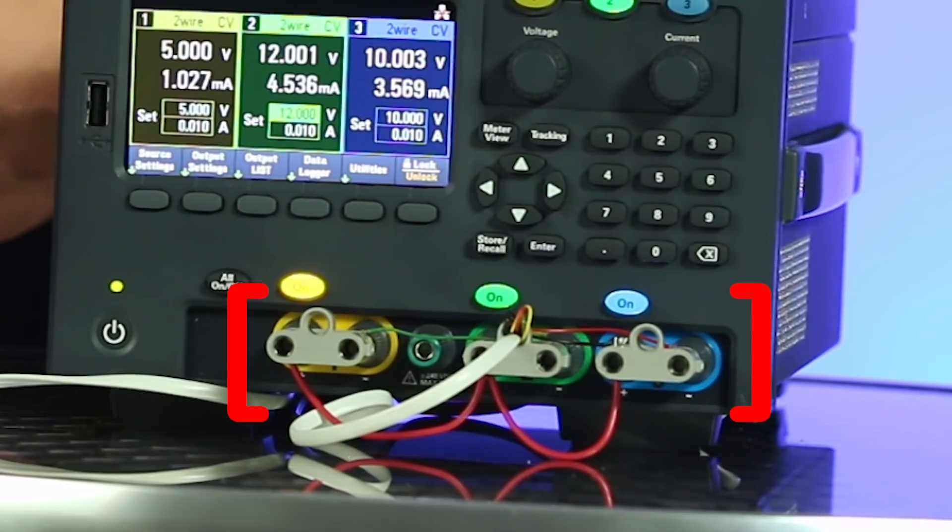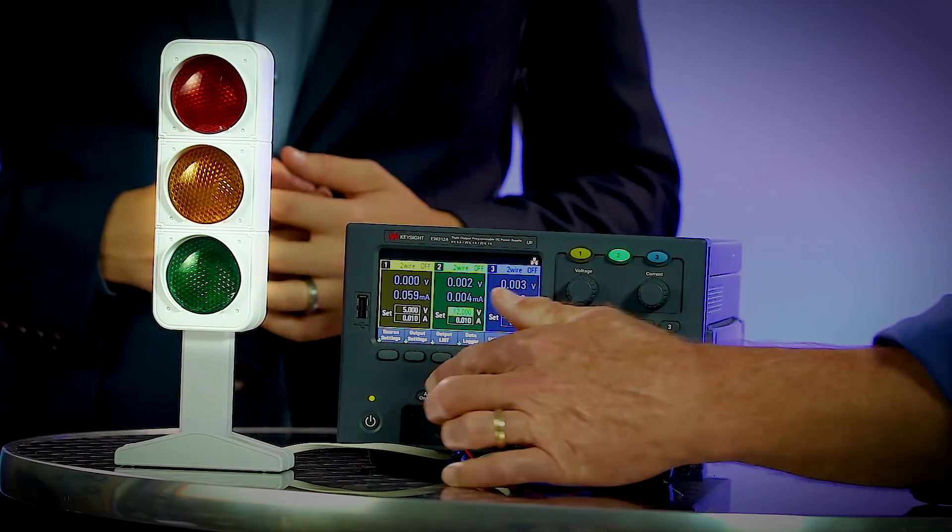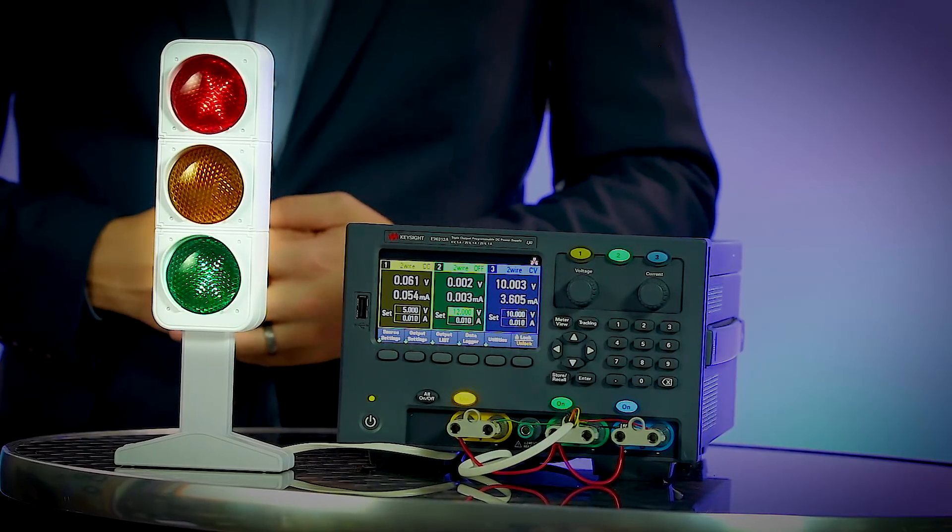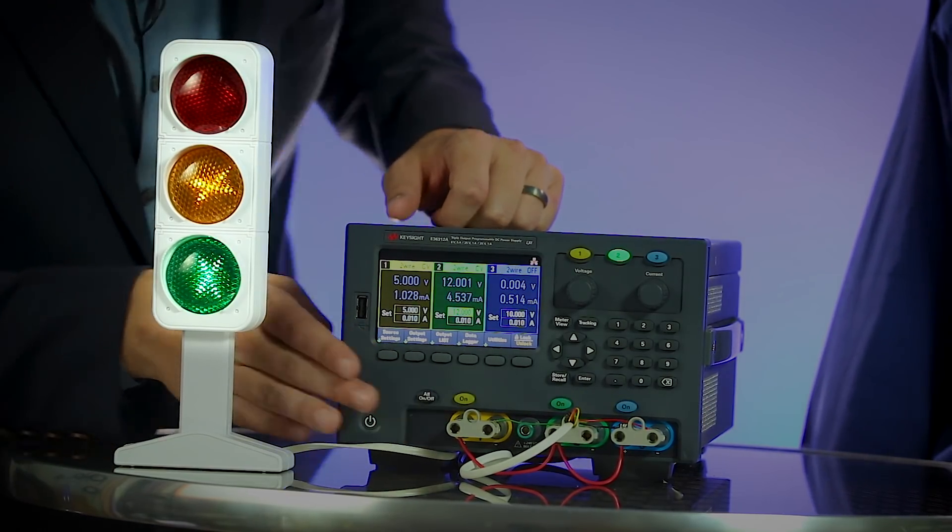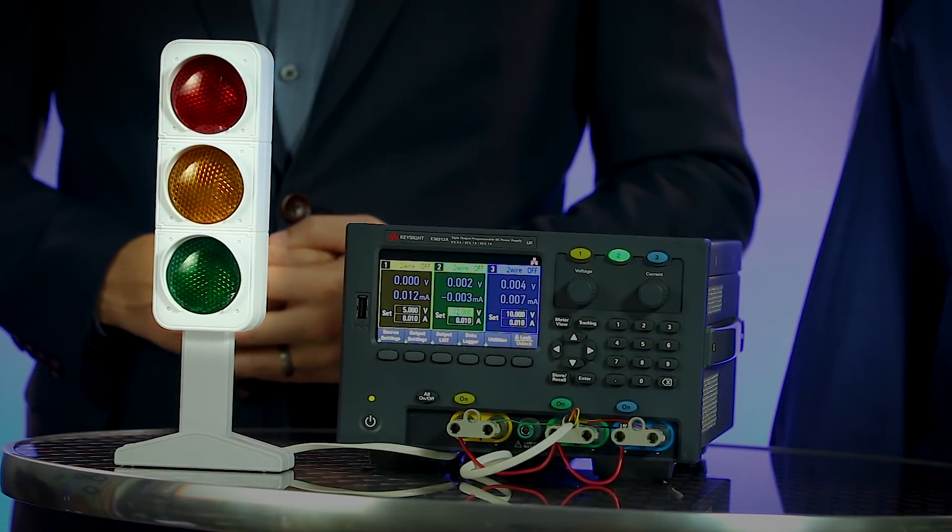Now that everything's set up, we're ready to connect to our lights and start our sequence. I'll press the on all button, and you can see the outputs turn on with their respective delays. Likewise, you can turn off the outputs and see the turn off delays. Some devices can be damaged if they're not powered down in the correct order.